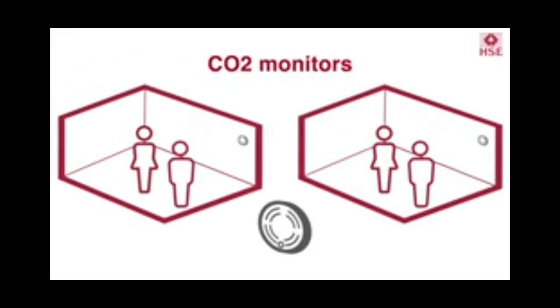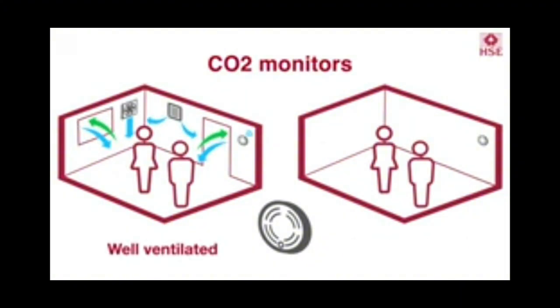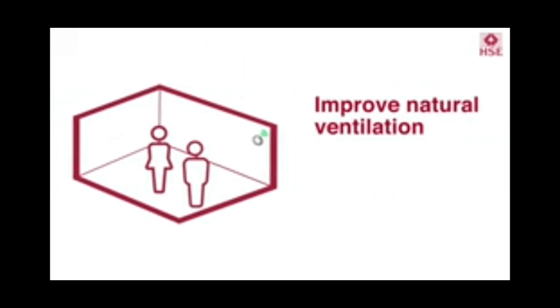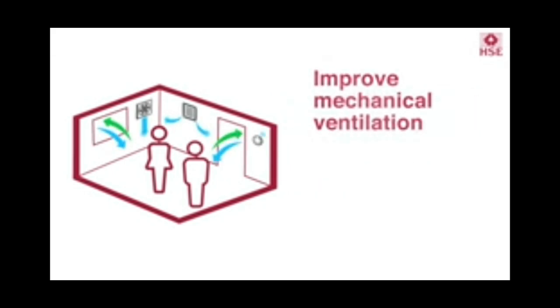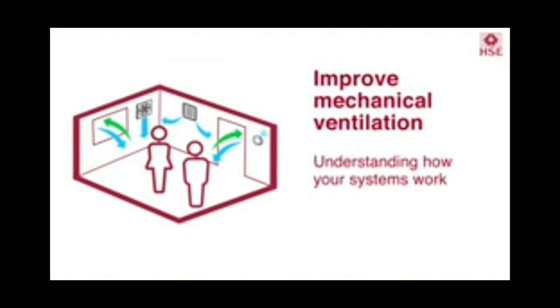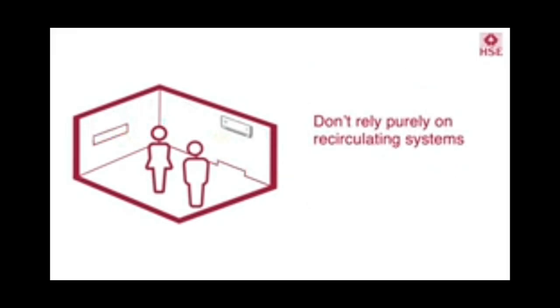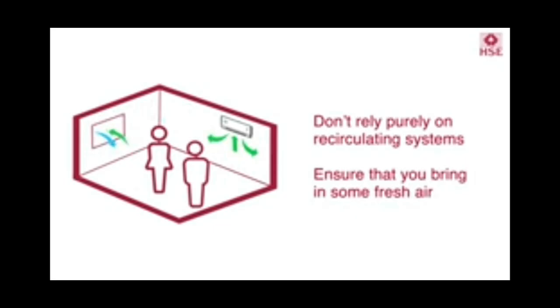CO2 monitors can help you assess if a space is well ventilated or badly ventilated. But monitors can only help you decide if there's a problem with ventilation in part of your workplace. They can't help you fix the problem, but they can tell you if your ventilation is working properly. You can improve natural ventilation by opening windows and opening doors. You can improve mechanical ventilation by understanding how your systems work and by making sure they're working properly. Don't rely on recirculation units. They don't bring in fresh air. They just move air around and will prevent you identifying poor ventilation.